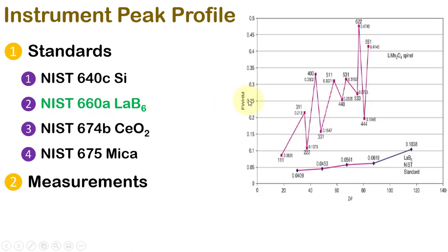In the instrument peak profile, we will have to take care in the choice of standards as well as during the measurements. Some of the standards are these in which we will consider the lanthanum hexaboride. Other materials can also be considered as standards provided that the variation in FWHM is almost linear with respect to an increase in two theta values.